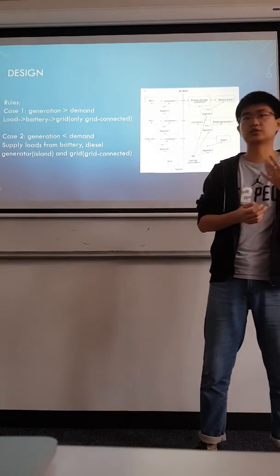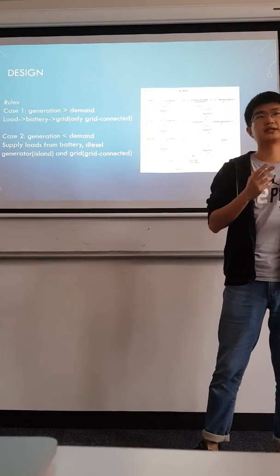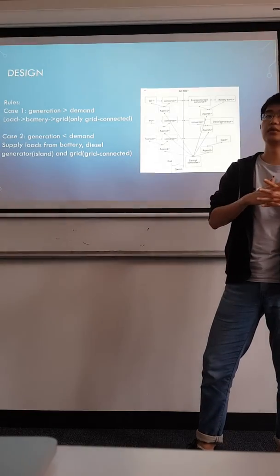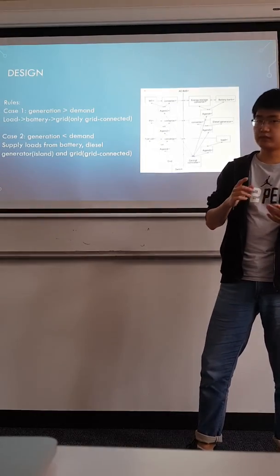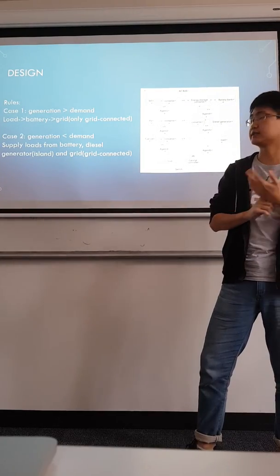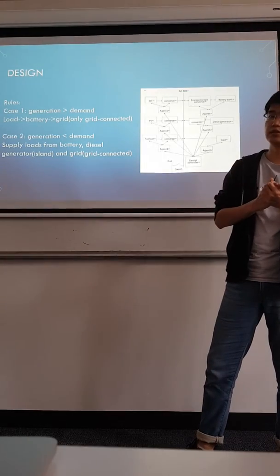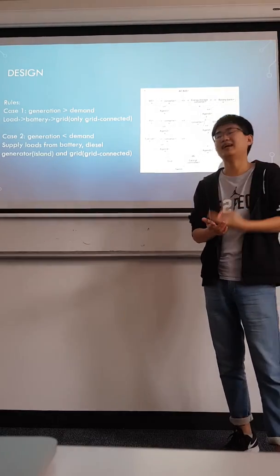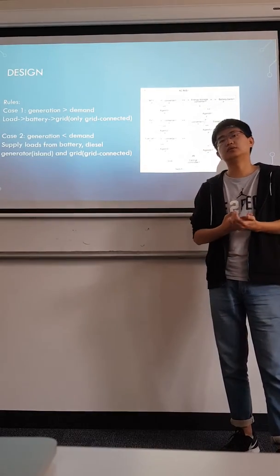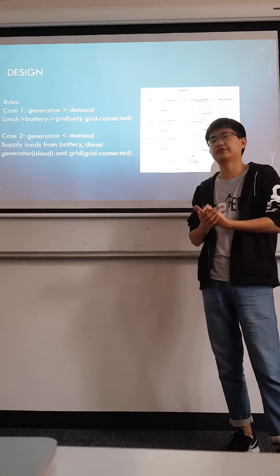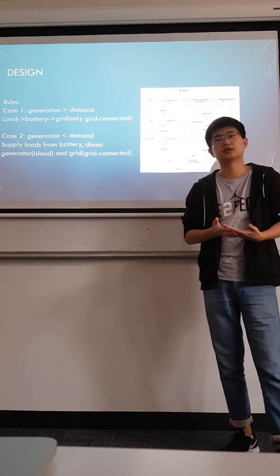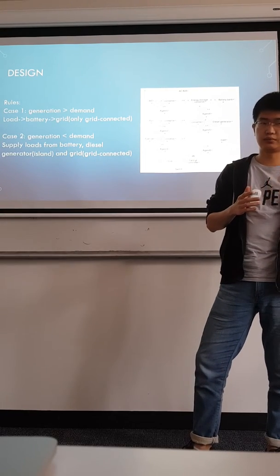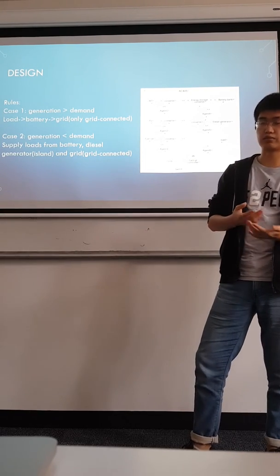When the total renewable energy generation is less than the whole load demand, it will supply the loads from the battery. When it's island mode, it will obtain the energy from the diesel generator, and when it's grid-connected mode, it will obtain the energy from the grid.